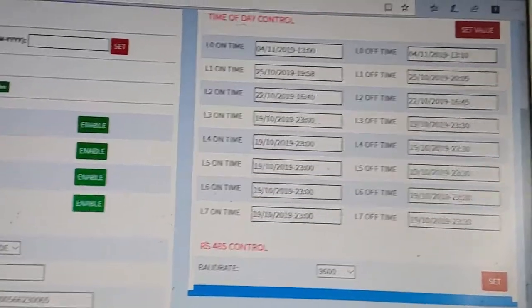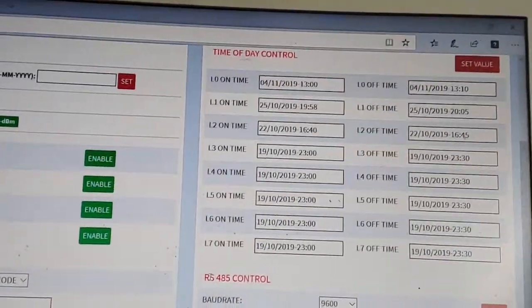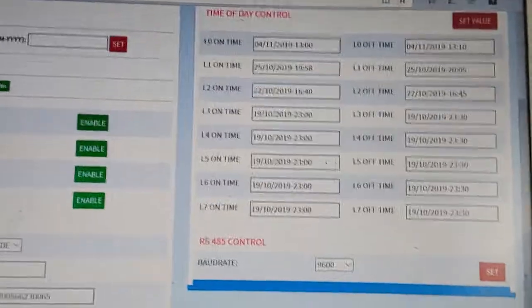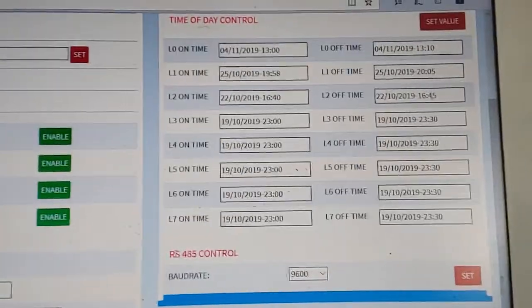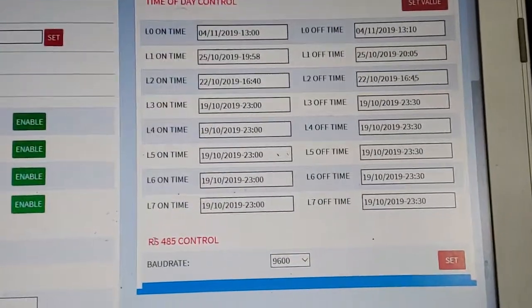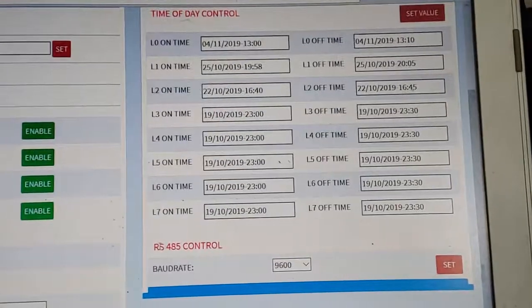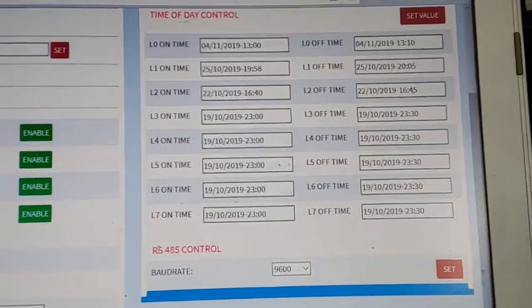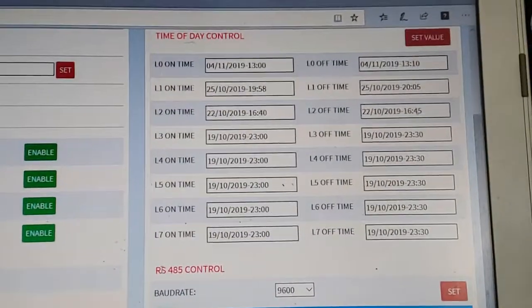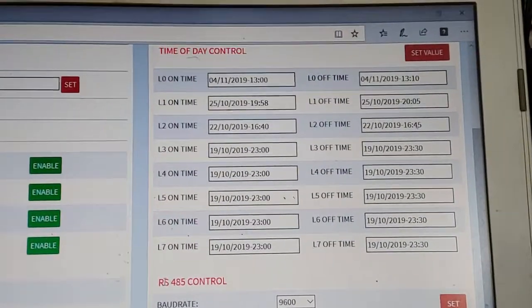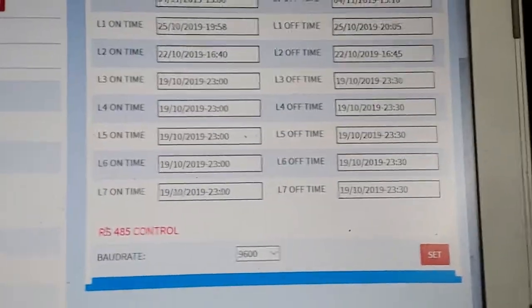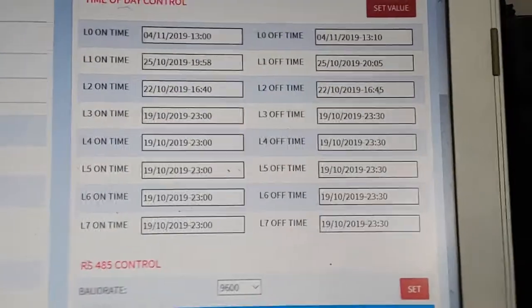If you yourself develop some device which you want to control through Branon, and that is not a direct load, you can use the RS485 control port, which supports Modbus. So you can use the Modbus communication protocol, and you can write the required engineering code by taking the device to the engineering mode, and you can use Branon to control your particular load, your particular device.